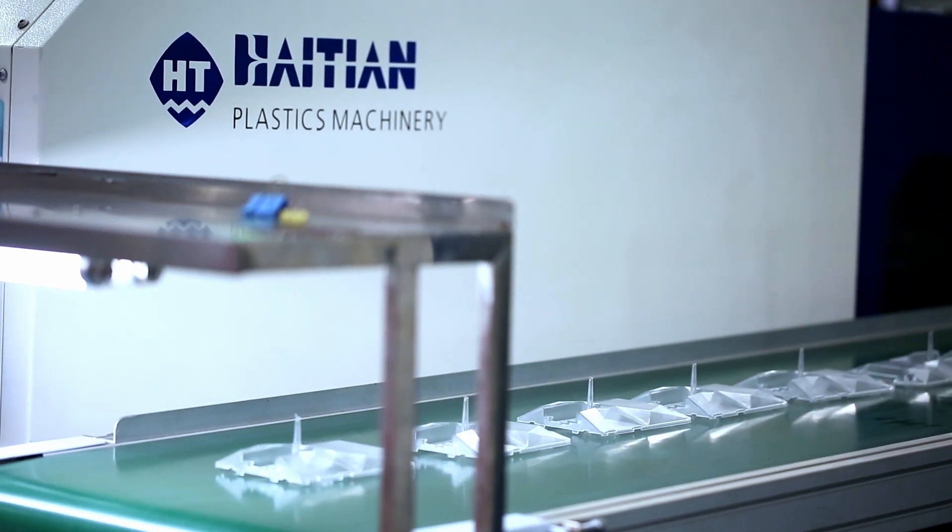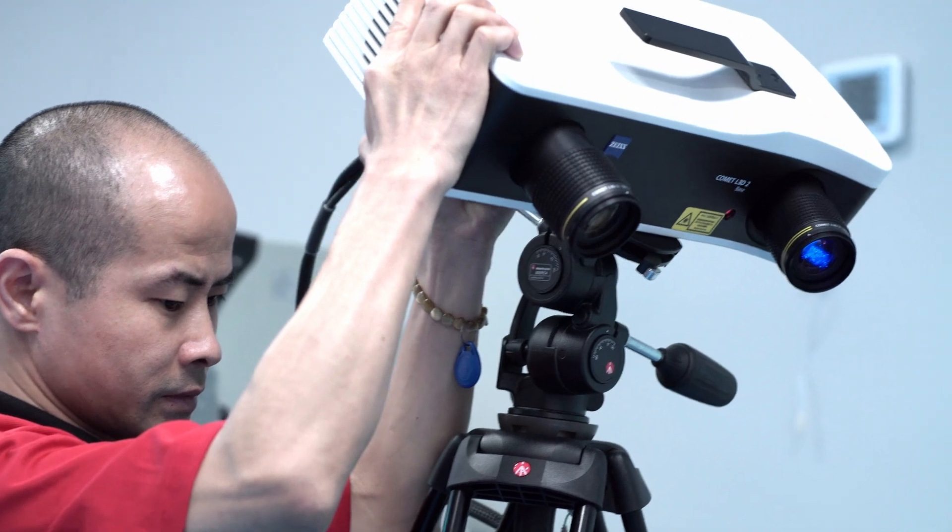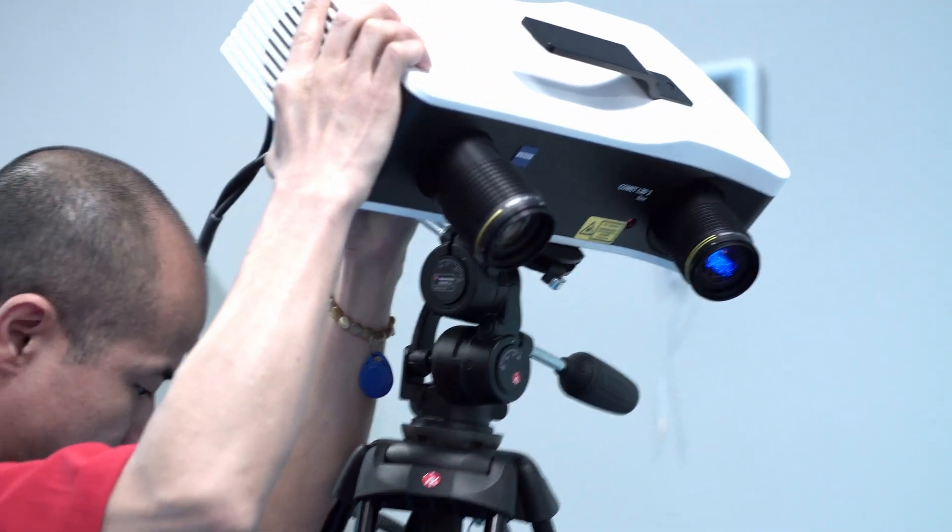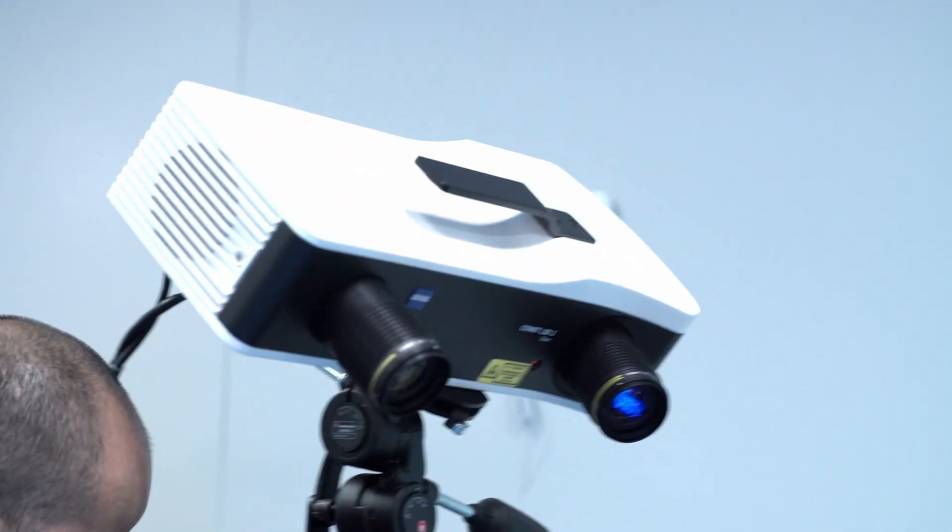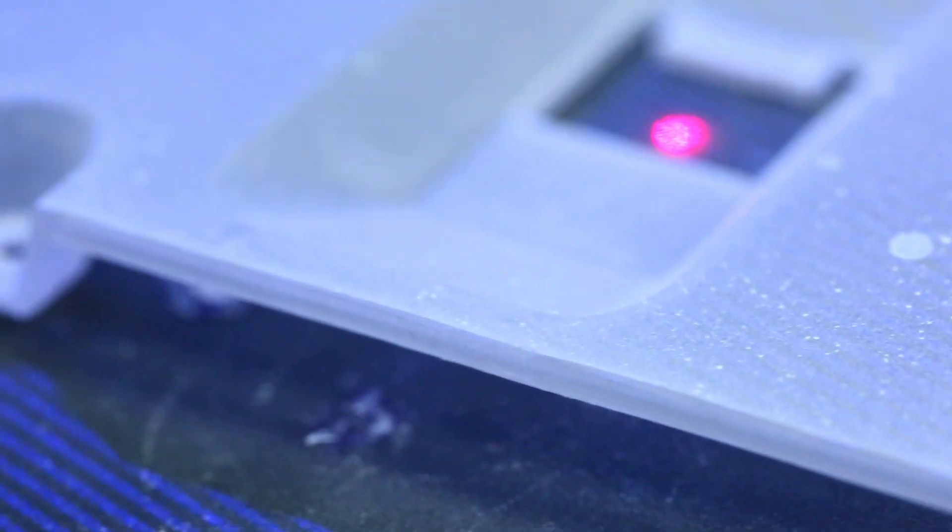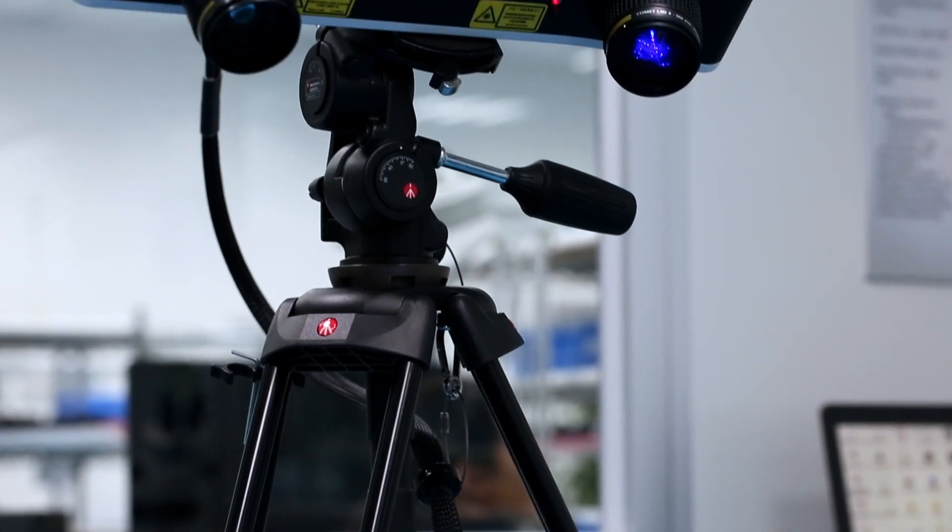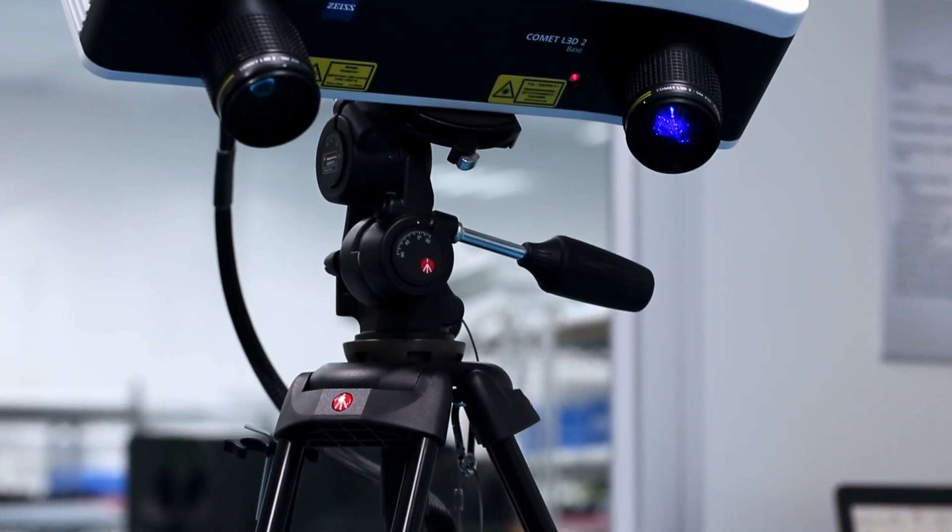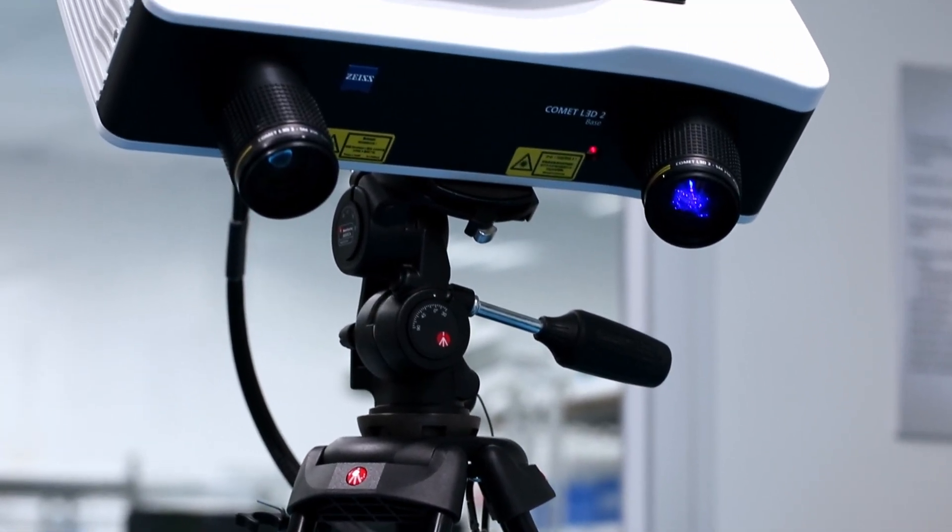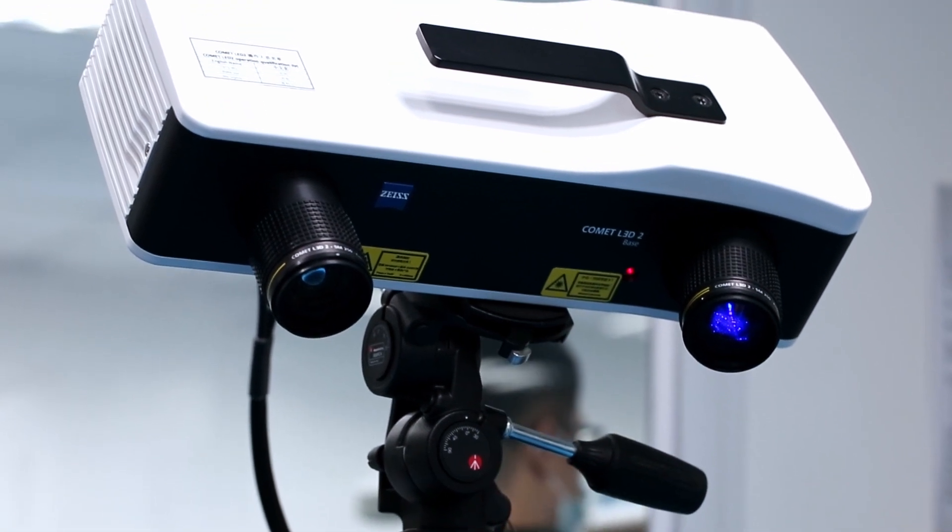There are a few potential limitations, however, and these apply to all optical systems. If a part is completely transparent or highly polished, it needs to be dusted with a fine spray of alcohol-based pigment. This doesn't harm the part, but it helps the LED light to focus on the surface. Also, the scanner might have problems with very small but deeply recessed pockets.